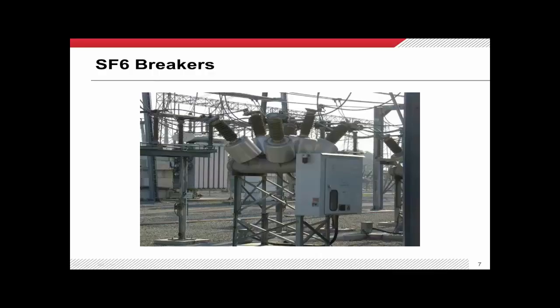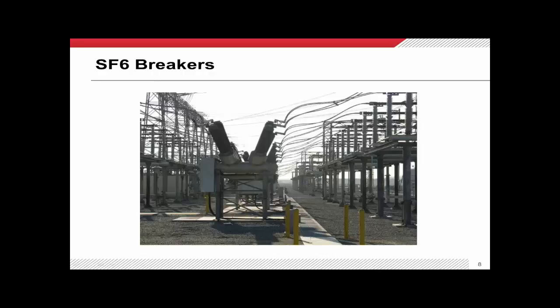Notice this little bar here on the breaker. This is in Southern California, and they have a problem with acid fog. On foggy nights condensation forms on the conductors, and without these standoff bars the condensation would roll and trickle down the bushings, leading to flashovers. That's a kind of interesting factoid about that design feature.